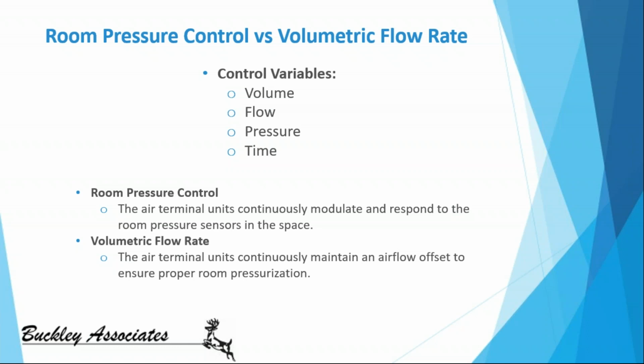If you have a flow controller, your flow is set. So your airflow into the space is set, which directly affects the volume flowing into the room. Therefore, our flow control is directly associated with volume control. On the other hand, the time variable is typically associated with a pressure controller. So what does all that mean?